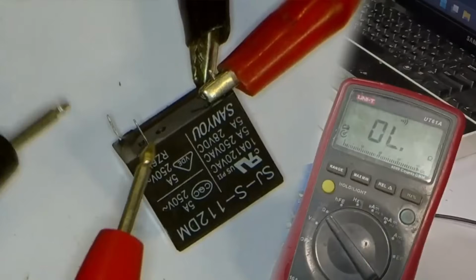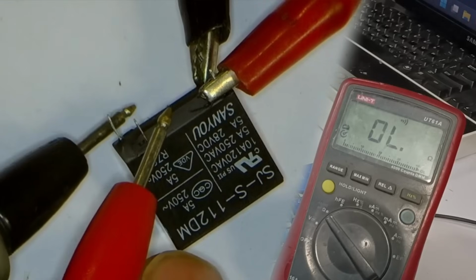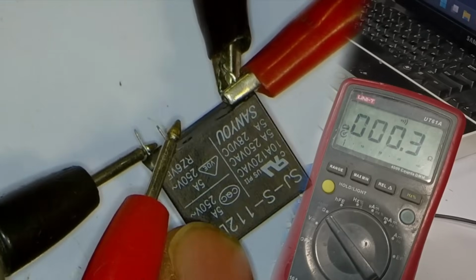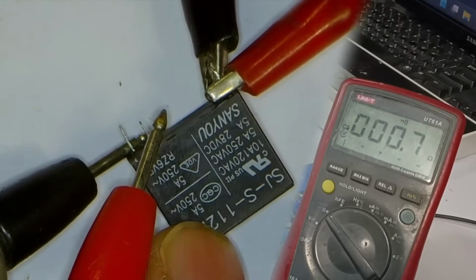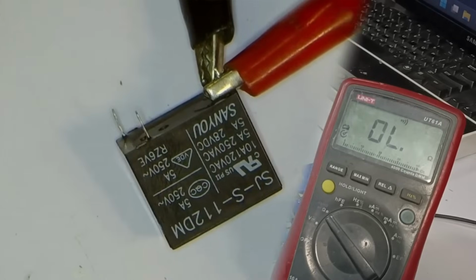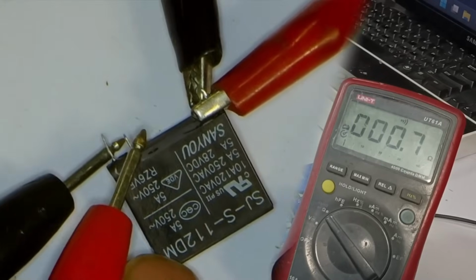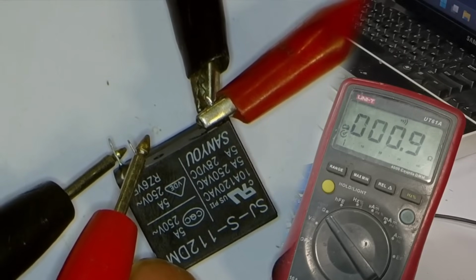First, I checked it without supplying voltage, and it shows disconnected. No continuity. Now, as soon as I turn on the supply, we can continuously hear the continuity beep sound. If I turn off the supply again, the beeping stops. When I turn it on again, the continuity sound immediately starts again. This means the relay is operating properly and switching correctly. After testing the relay, we found that it is working perfectly fine and there is no problem with it.